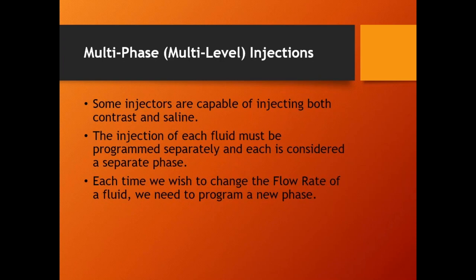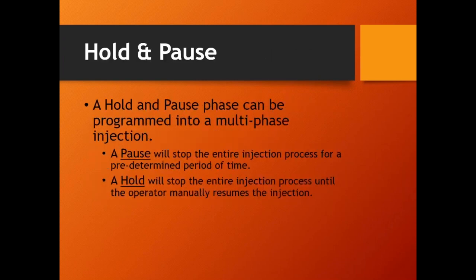Does any of that information get stored like in a DICOM file or anything that goes to the patient image data? Yeah, flow rate, volume, there's actually DICOM headers for the specific contrast. There's a lot of parts of DICOM that can carry information. How often they actually do it varies, because the only way you'd be able to add it to DICOM is if the system interfaces with the actual MRI or actual CT system. They do that, but not always. A lot of times they do, a lot of times they don't. Typically, the signal line is all they have connected. All right.